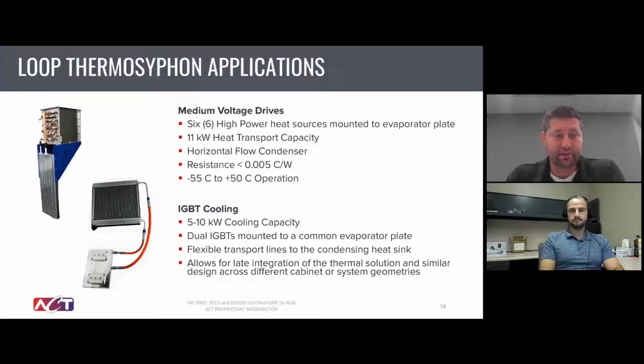And then the bottom solution here, similar type application. This was a 5 to 10 kilowatt cooling capacity. But what we're showing here specifically is the orange hosing that you see. And this was somewhat of what I was alluding to in the last example as well. You have the ability to have a remote condenser and flexible lines between the evaporator and condenser. So this allows designers of these cabinets to integrate thermal solutions late when it's already fairly populated and packaged. It also allows you to run fairly long flex lines.